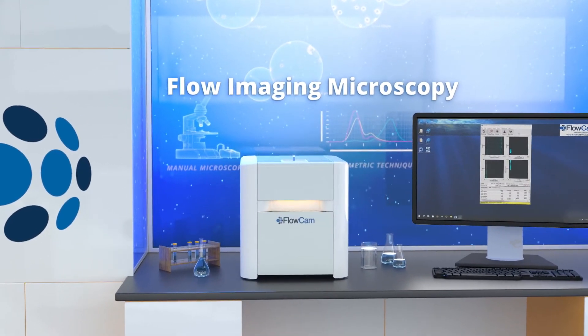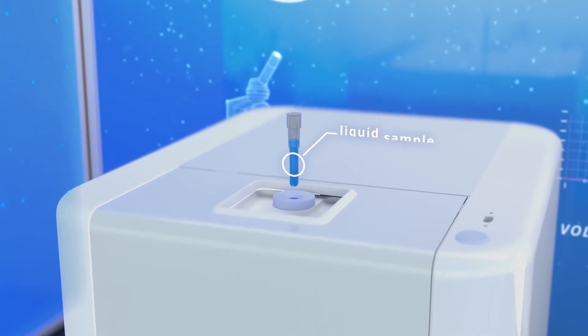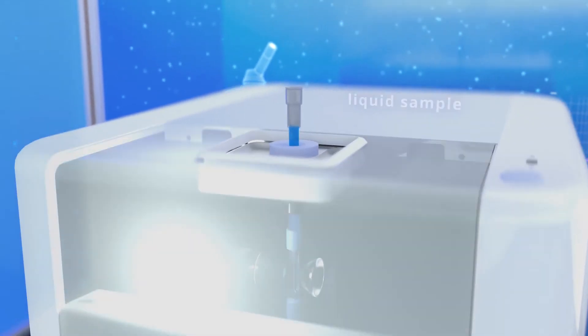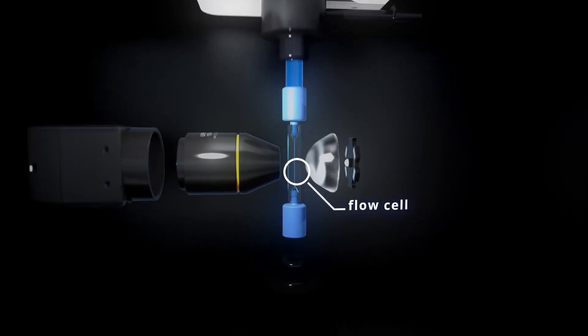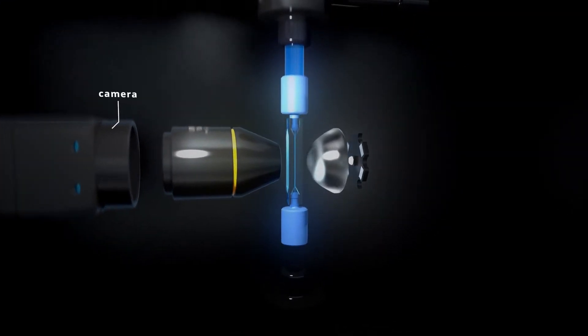Here's how it works. After a liquid sample is introduced into the top of the FlowCam, a software-controlled syringe pump pulls it through the flow cell and past the optical system within the device.